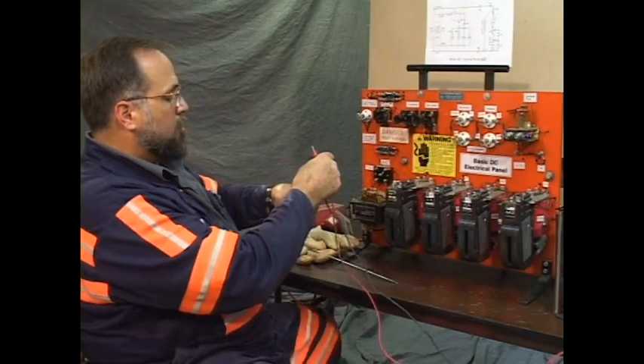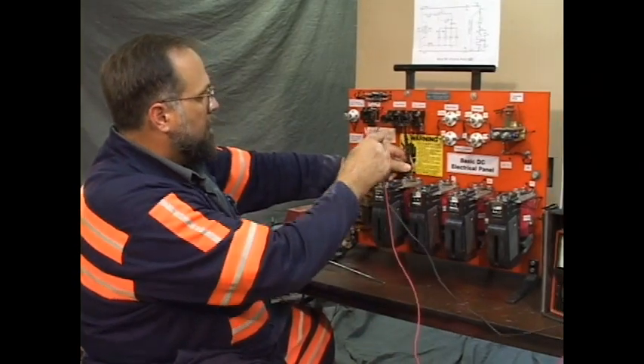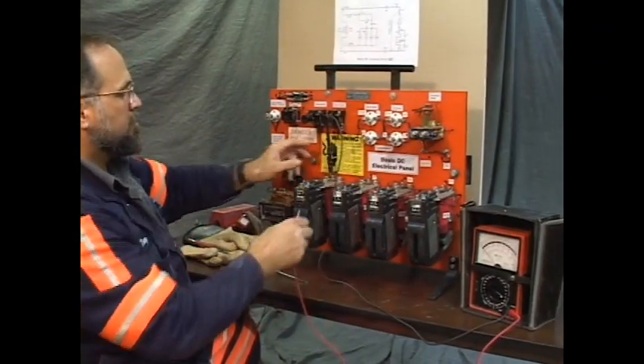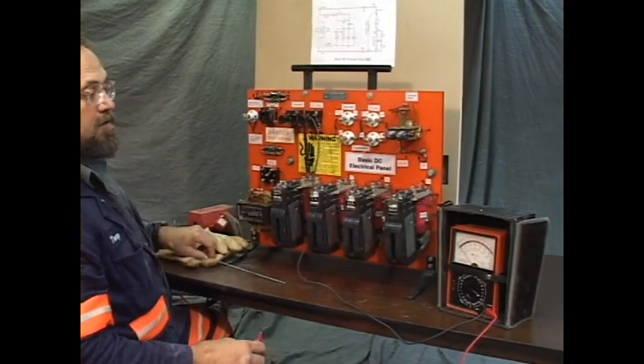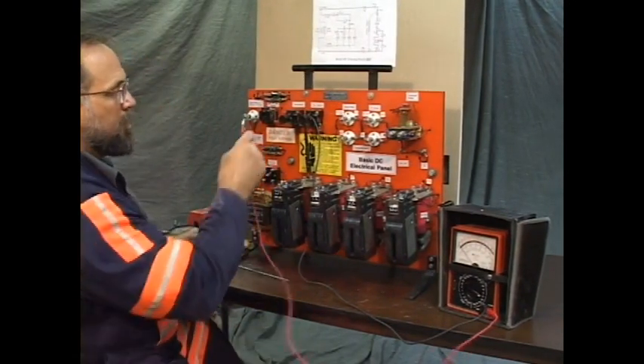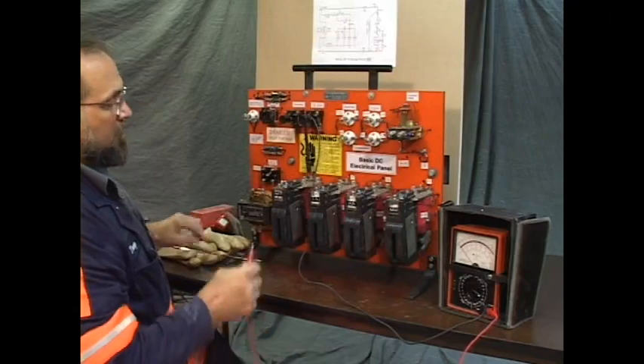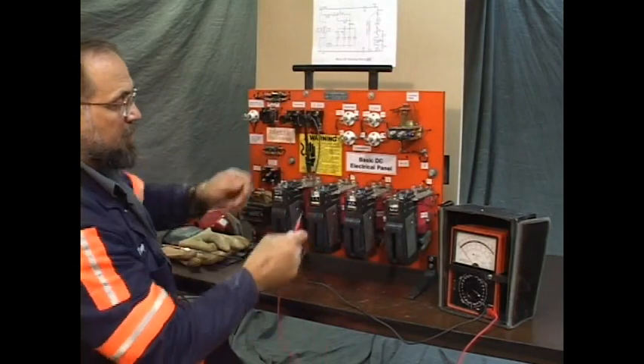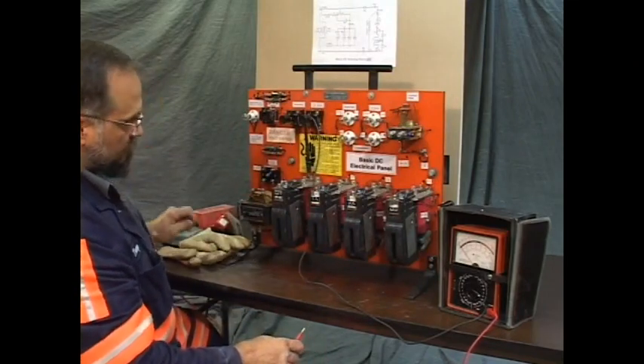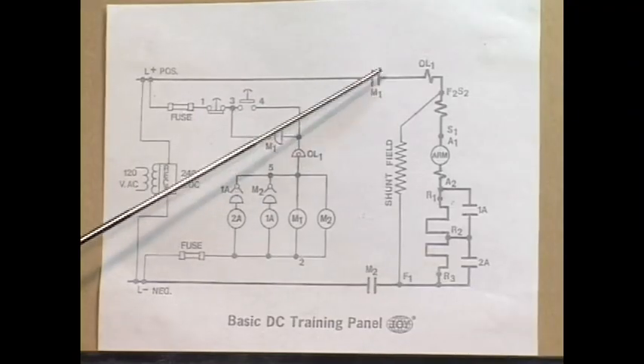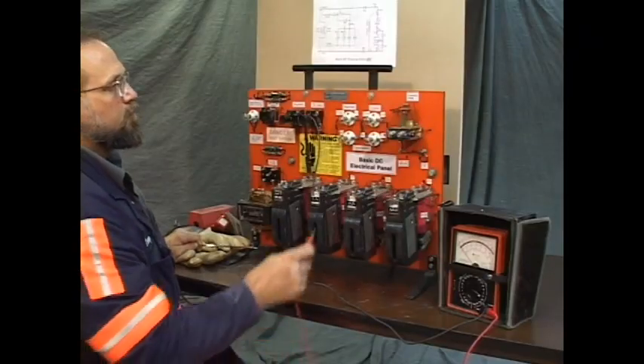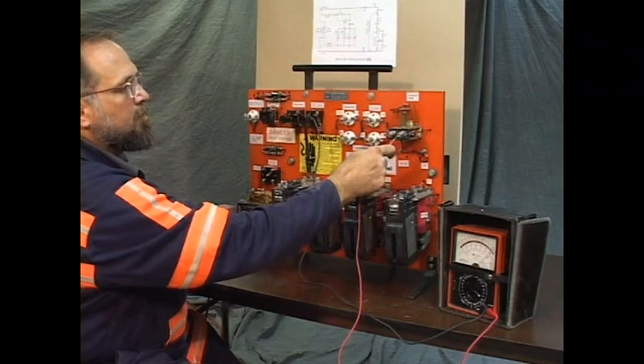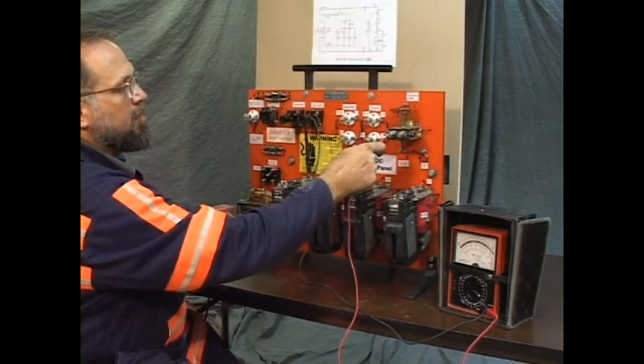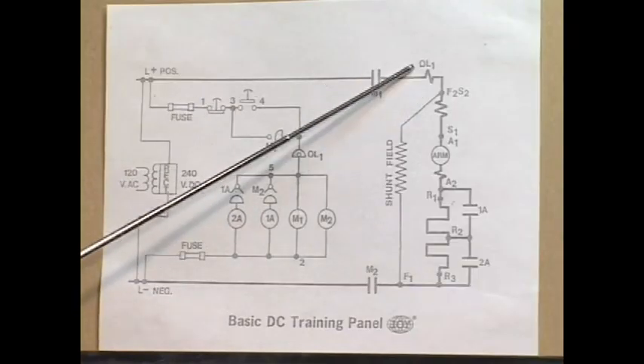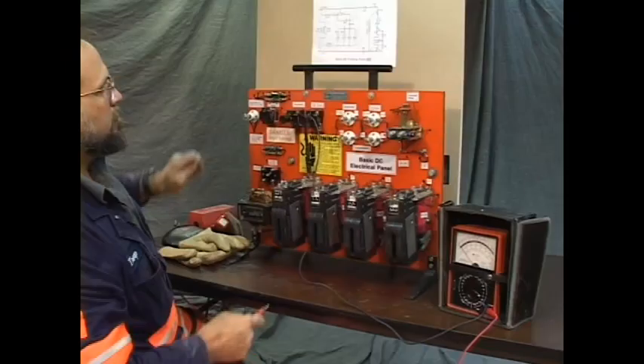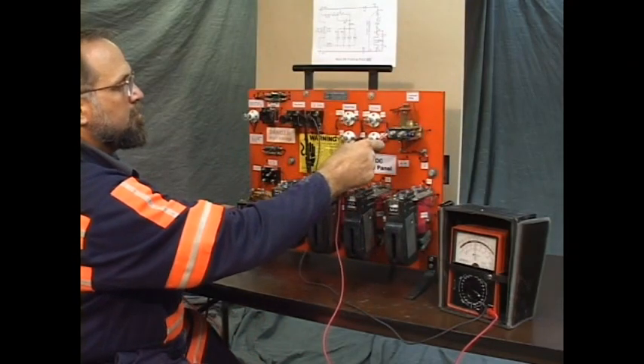I'm going to attach my probe. Again, I want to make a connection and only manage one probe at a time and build upon those checks so that I don't omit by changing places with the leads. I'm attaching my probe here. That's this point right here. First point it goes to is this point. That's good. Then it goes here. That's these two places here. This F2, S2. You can see the two wires.